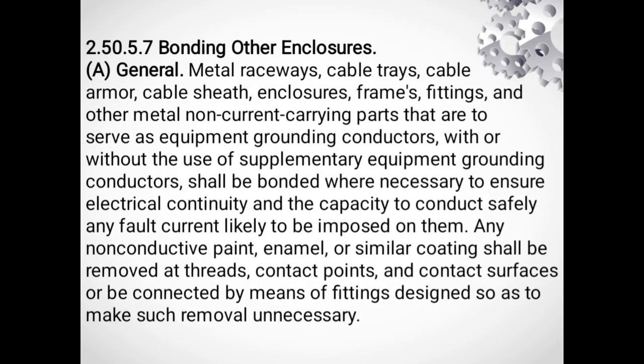2.50.5.7 Bonding other enclosures. A. General. Metal raceway, cable trays, cable armor, cable sheath, enclosure, frames, fittings, and other metal non-current carrying parts that are to serve as equipment grounding conductors, with or without the use of supplementary equipment grounding conductors, shall be bonded where necessary to ensure electrical continuity and capacity to conduct safely any fault current likely to be imposed on them. Any non-conductive paint, enamel, or similar coating shall be removed at threads and contact points and contact surfaces, or be connected by means of fittings designed so as to make such removal unnecessary.